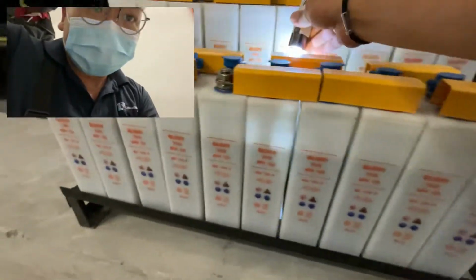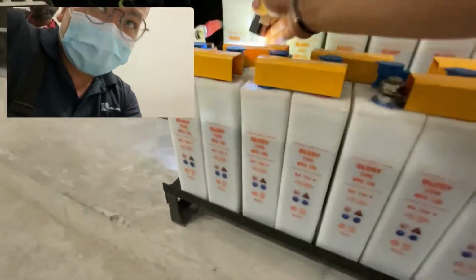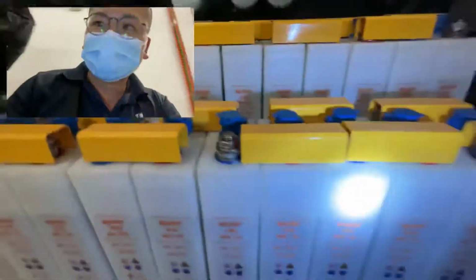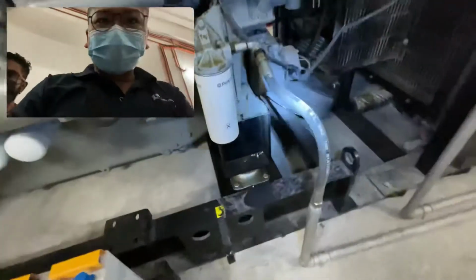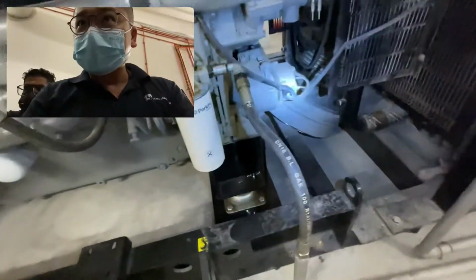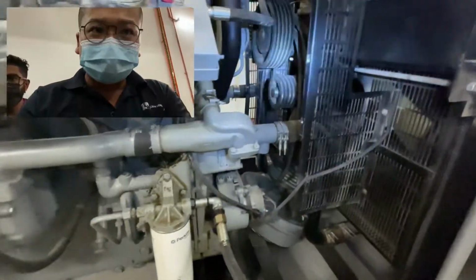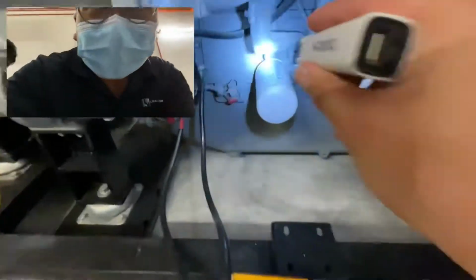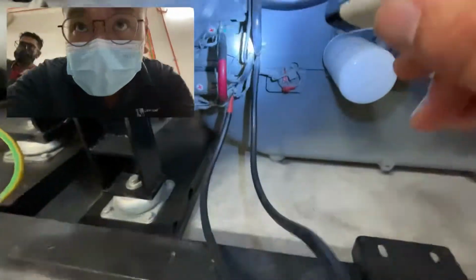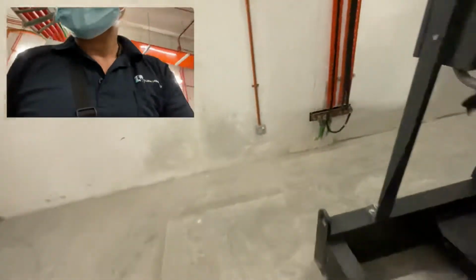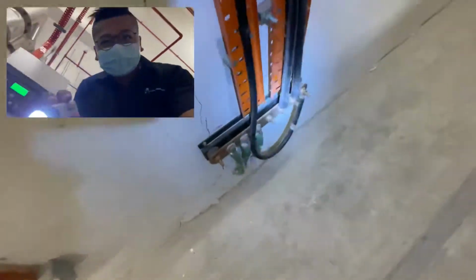So we're going to see the battery water level. All is at high level. Okay. Then check for any leakages of fuel. Okay, belting will be under repair sooner or later. Okay. No leakage. Starter cable connection is firm. Okay. Earthing, neutral earth and earthing termination good.